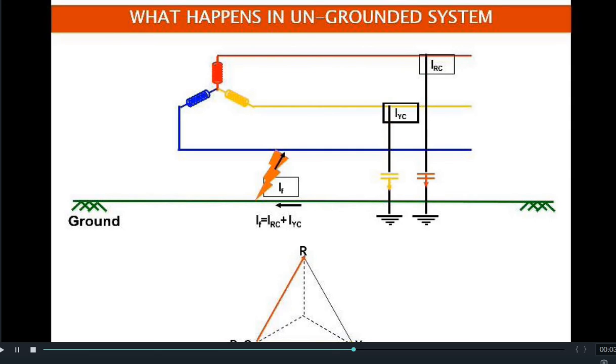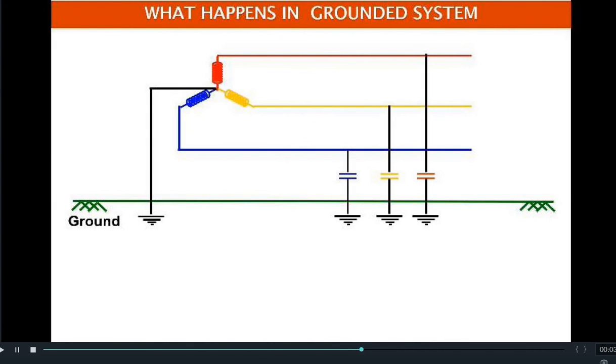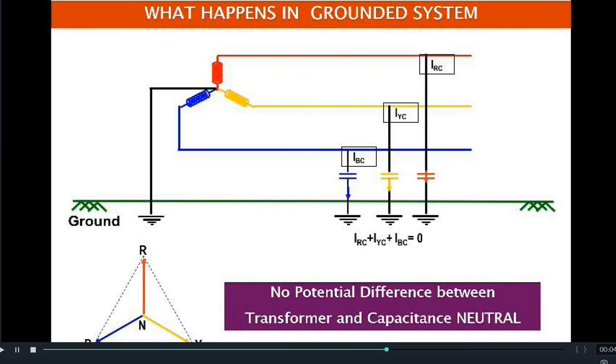In a grounded system, the neutral of the three-phase system is grounded through a connection, imposing the neutral voltage of zero volts onto the ground and making the ground potential zero. When the lines are charged, as in the ungrounded system, there will be capacitive currents from the lines towards the ground, and the summation of IRC, IYC, and IBC will be zero. There will be no potential difference between the transformer and the capacitive neutral.